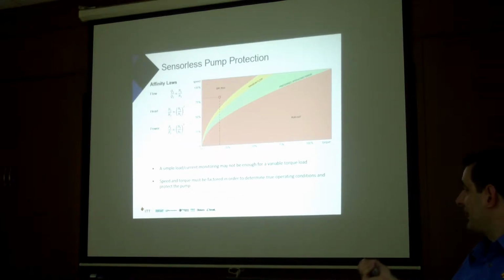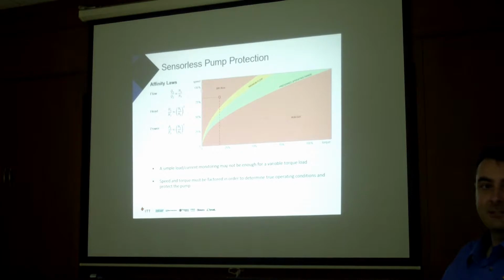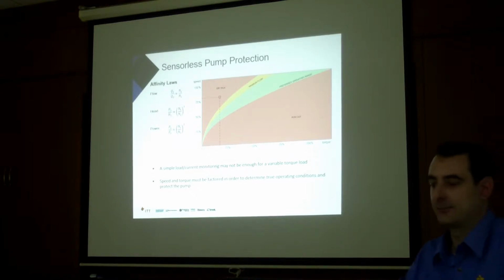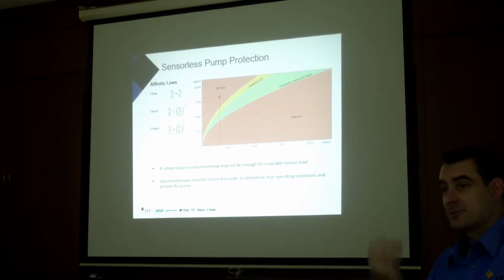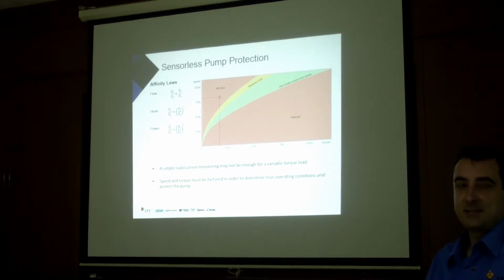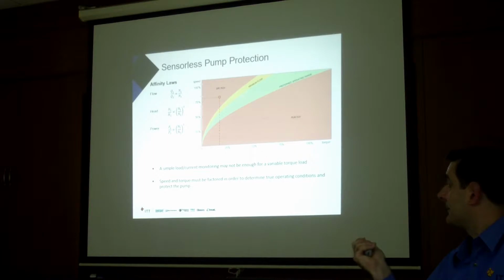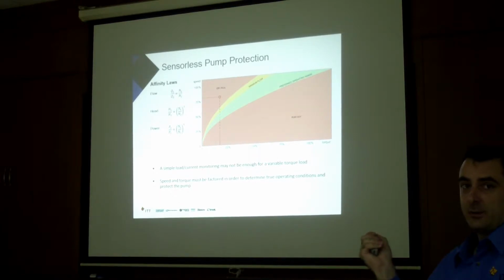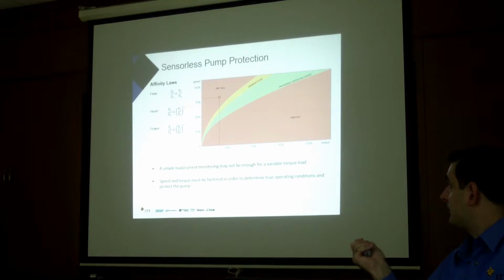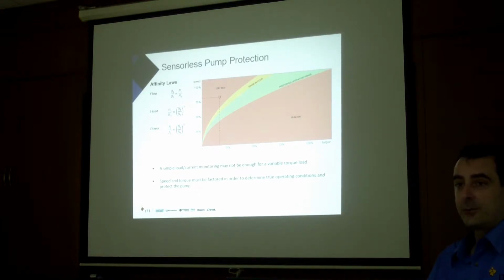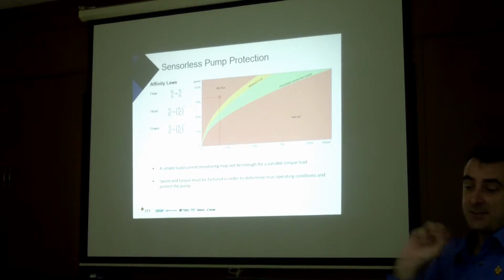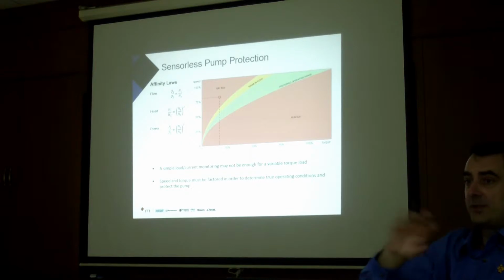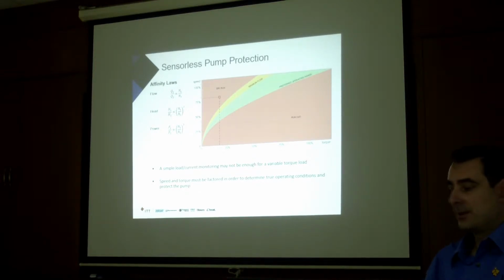Some variable speed drives might allow you to put 2 or 3 points, different torques versus different speeds, but it's still a guess. With the Pump Smart, we don't guess, we know. Through affinity laws, we calculate. Also, our torque response, the reason we use the ABB ACS880, is that this torque value is very accurate. Because that's accurate, we can do this accurately. Also, we can accurately tell the customer that they're at minimum flow compared to dry run. We can tell them the difference: acceptable, minimum, dry run, and run out. So we can tell all three bad situations, and we can send that to the customer as a warning, a fault, anything they want, so they can change the way they operate.